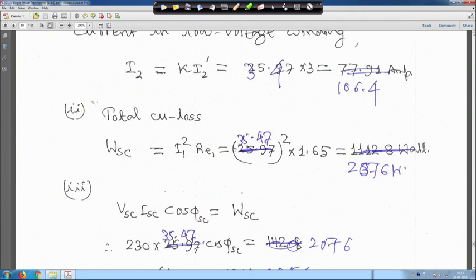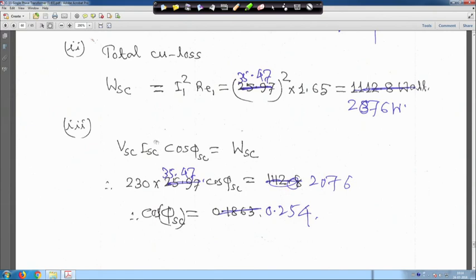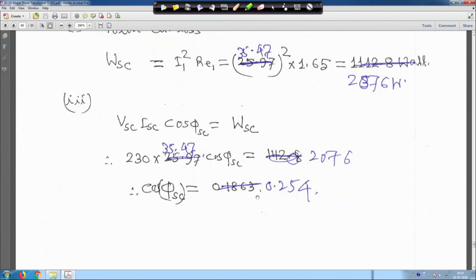Total copper loss W_SC equals I_1² × R_E1 = 35.47² × 1.65 = 2076 watts. Using V_SC × I_SC × cos φ_SC = W_SC: 230 × 35.47 × cos φ = 2076, giving power factor cos φ = 0.254.